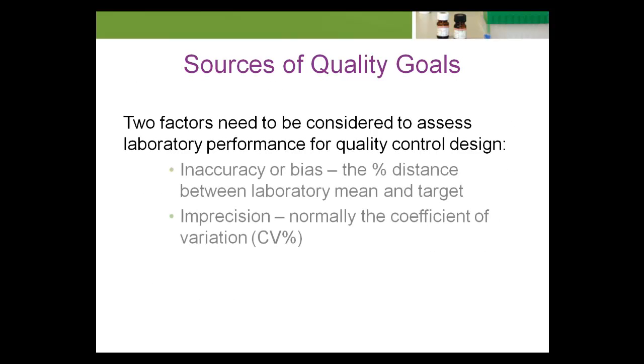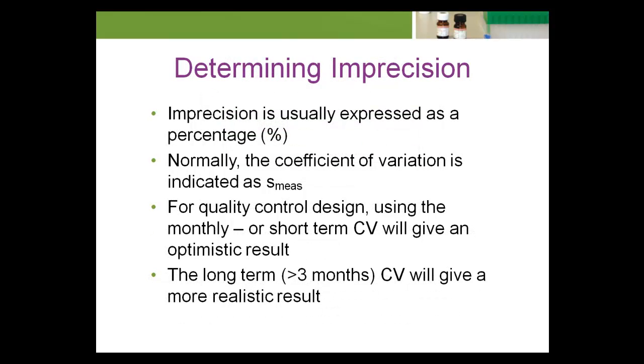The bias and imprecision for each test must be determined. Bias or inaccuracy can be thought of as the calibration difference between where a test is calibrated and where it should be calibrated. Imprecision is expressed as the coefficient of variation, or the analytical CV. In the technical literature, the analytical CV is frequently represented as S-measure.